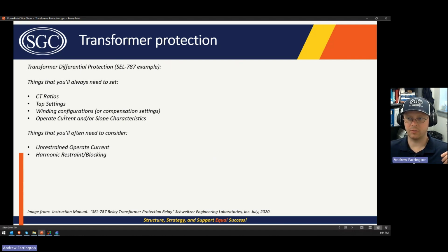Then you'll want to set the winding configuration settings, or they're also known as compensation settings. And then you'll need to determine what the operate current or slope characteristics are. And things that are often included as additional features in a microprocessor-based relay are things like the unrestrained operate current, which is a setting just like bus differential relaying. Usually you operate on a slope that relates your operate current to a restraint current.